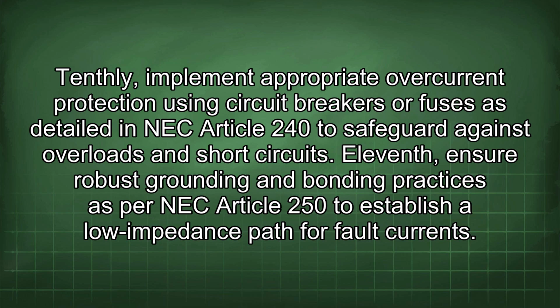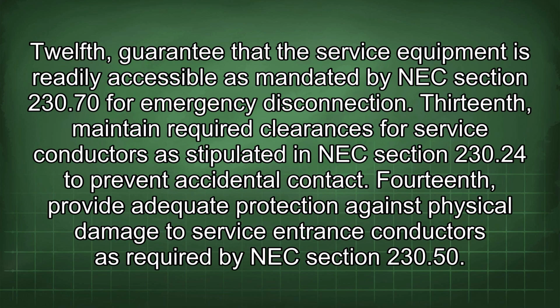11th, ensure robust grounding and bonding practices as per NEC Article 250 to establish a low impedance path for fault currents. 12th, guarantee that the service equipment is readily accessible as mandated by NEC Section 230.70 for emergency disconnection. 13th, maintain required clearances for service conductors as stipulated in NEC Section 230.24 to prevent accidental contact. 14th, provide adequate protection against physical damage to service entrance conductors as required by NEC Section 230.50.